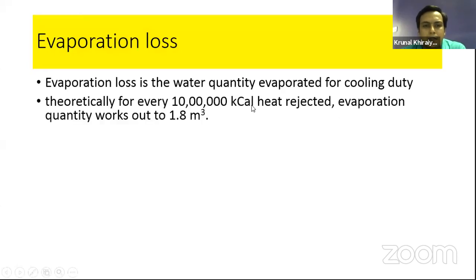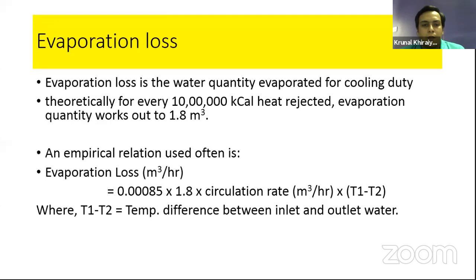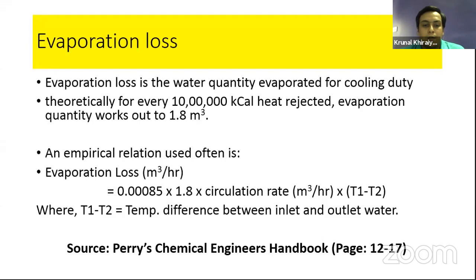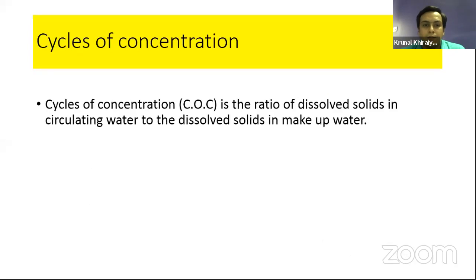Theoretically, yes, this is a very important parameter, because you cannot have a direct formula for the evaporation loss calculations. So here is one empirical formula which is largely used in the open literature, and I'm taking it from the Perry's Chemical Engineers' Handbook, page number 12 to 17. 0.00085 times 1.8 times the circulation rate in cubic meters per hour times the temperature difference. This is an empirical formula generally used by industry people for the calculation of evaporation losses.